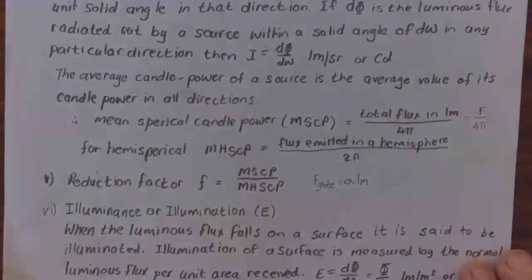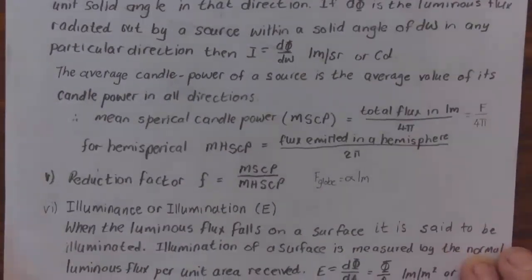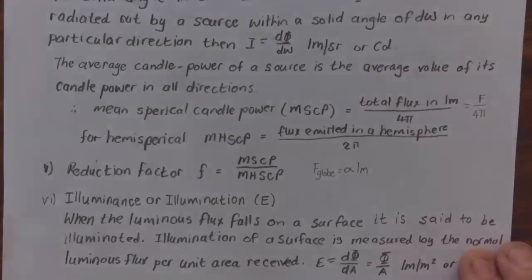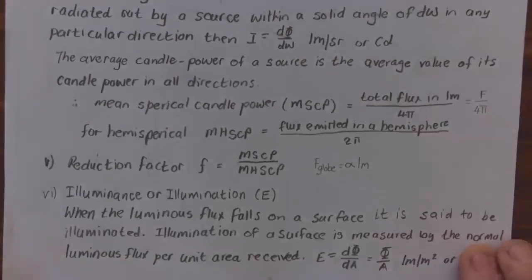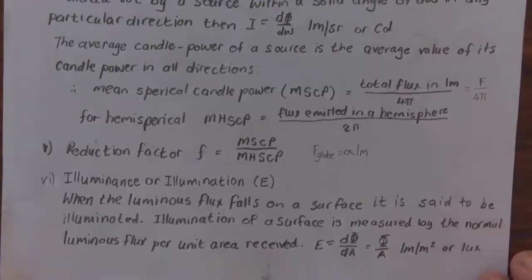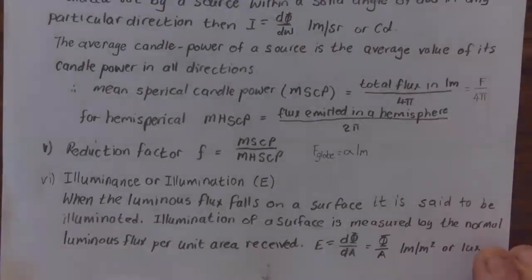The average candle power of a source is the average value of its candle power in all directions. The mean spherical candle power is the total flux in lumens divided by 4π, which is F/4π. For hemispherical flux emitted in a hemisphere, it is divided by 2π. The reduction factor f is the mean spherical candle power divided by the mean hemispherical candle power.